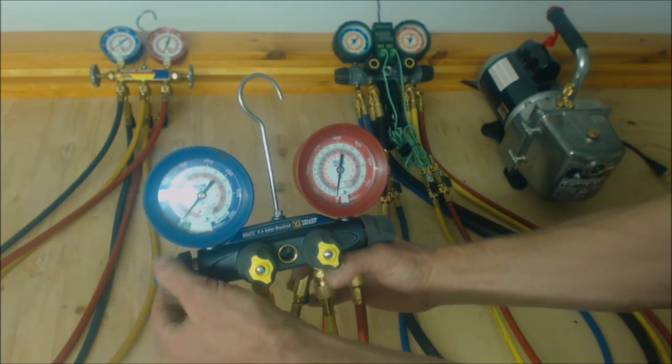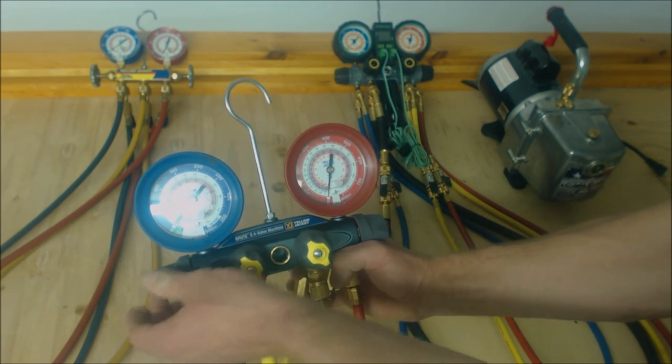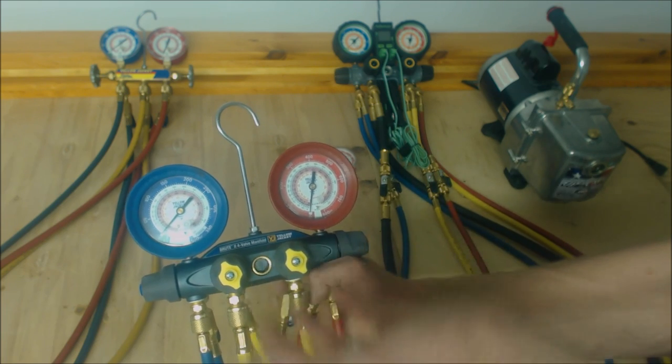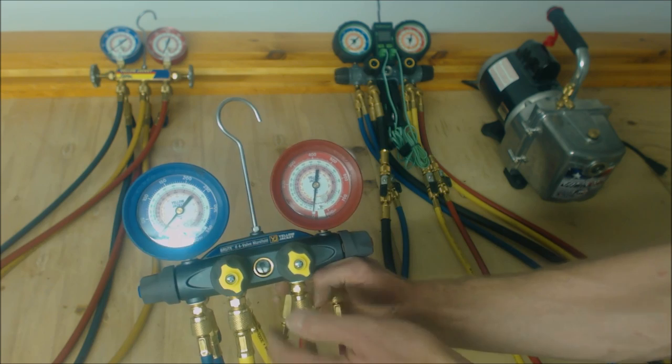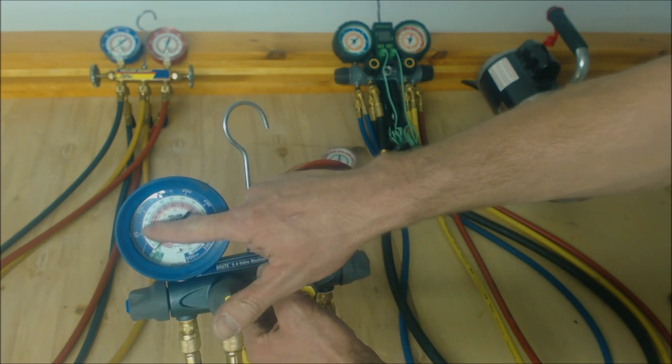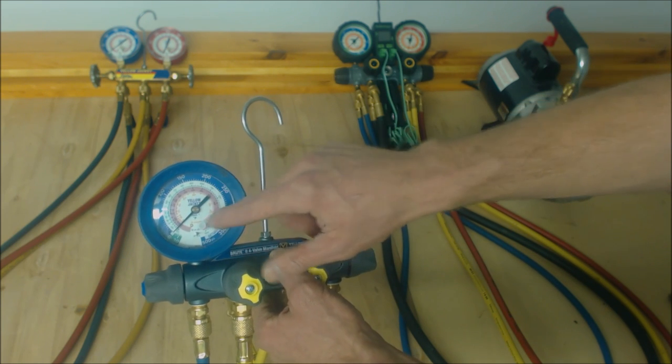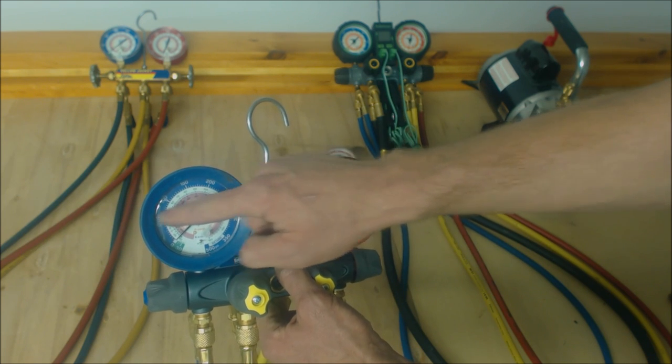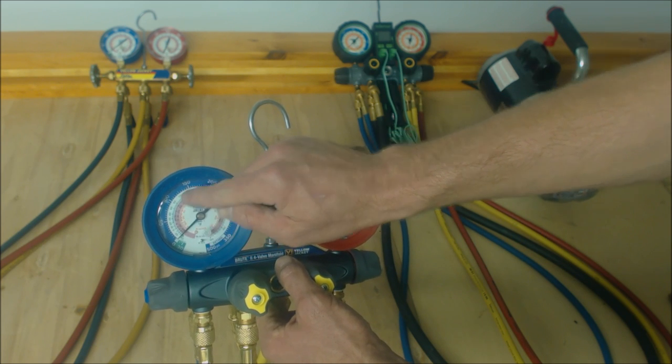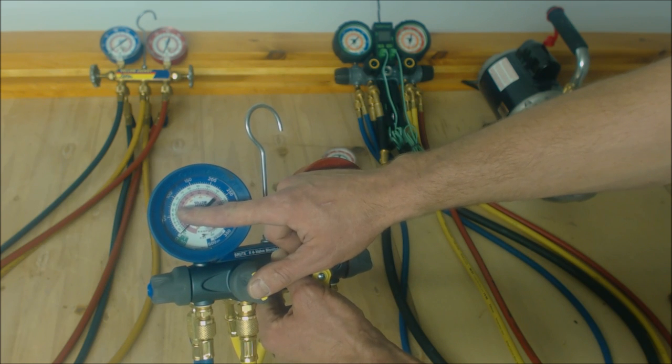I do have a lot of people asking me why I don't switch to digital gauges. My whole theory on the whole thing is that when I'm teaching and when I'm doing this, I want to have the most thinking into it that is possible. I know that sounds like I'm making more work for myself, but when there's a problem on the system - everything's fine until you have a problem with a system - then you need to start really thinking about what's happening to the saturated state in that system. So I want my students to look at the pressure, convert it to a saturated temperature. The outside ring is pressure right here. Then you have on this one three inner rings that will line up with the dial. The green is R22, the pink is R410A and the orange is R404A. You bring it in from whatever pressure it is. Say it's at 75 PSIG, I can actually bring it in to 44 degrees R22 if I use this gauge for R22.